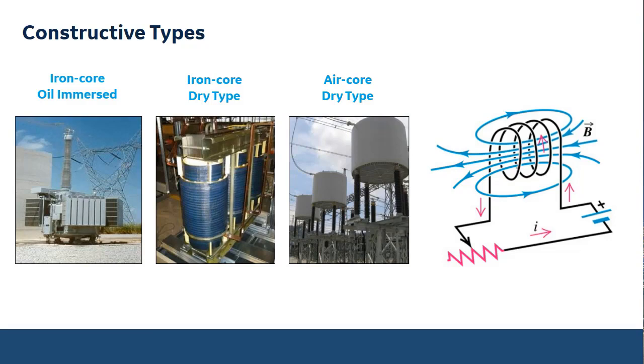The second one is iron core dry type. The main difference is that it has an iron core, but it doesn't have oil. The main application for this type of technology would be low voltage, or where you need to fit a reactor in a very small area. So again, it has an iron core. You need to keep the magnetic field inside of this core, and it also needs to be dry type and fit inside an enclosure or very limited space. So then comes the third technology, air core dry type, which I'm going to focus on today.